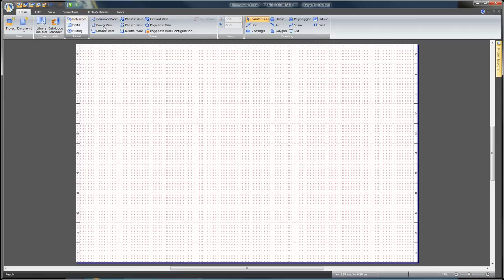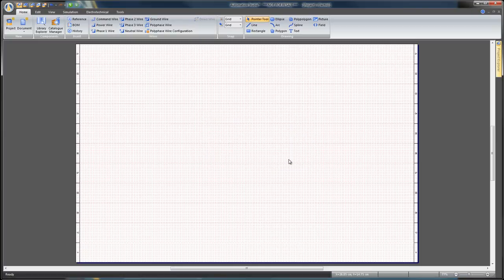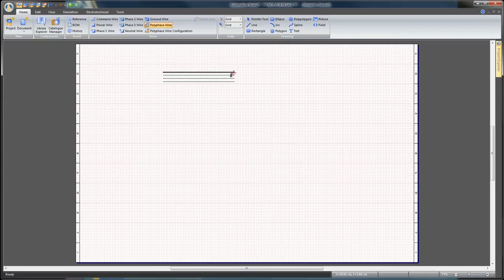Back on the Home tab, select Polyphase Wire Configuration, choose Custom option, select L1, L2, L3, and N in the Custom Combo boxes, and click Apply. Click on the Polyphase Wire icon from the Home tab and draw a polyphase wire.